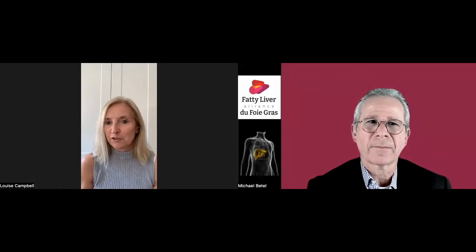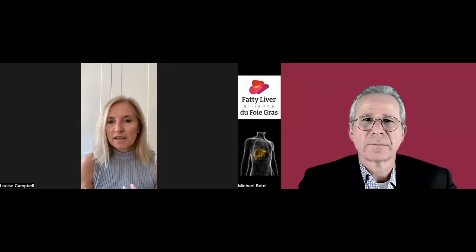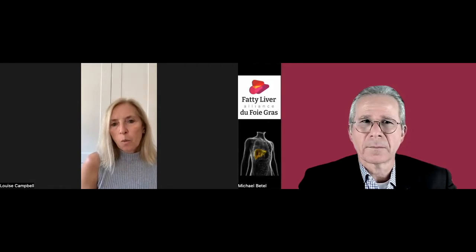Liver disease scares the pants off most physicians in most specialties, and therefore it becomes too technical and we just refer on. But FibroScan, in essence, is a very simple tool that basically sends a 50-hertz sound wave through your liver and wobbles it. It has an element of one-dimensional ultrasound, which means it's regulated in some countries like the UK but not regulated in others. But essentially, it's a non-invasive assessment of liver stiffness — not a confirmation of liver disease, not a confirmation of fibrosis, but an assessment to narrow down people who may have livers at risk.